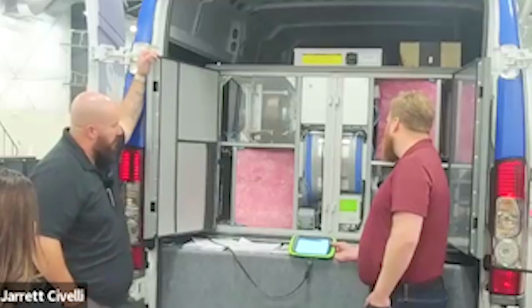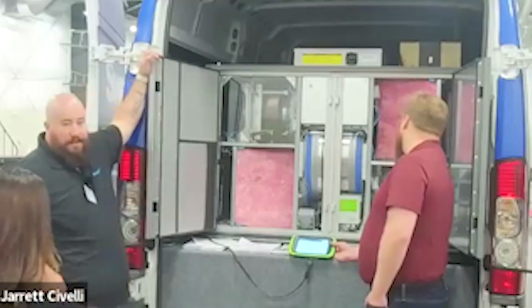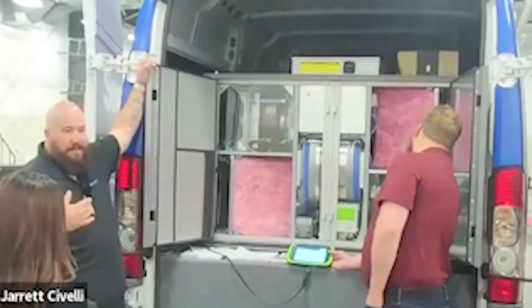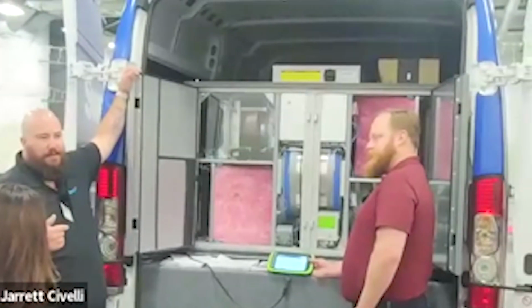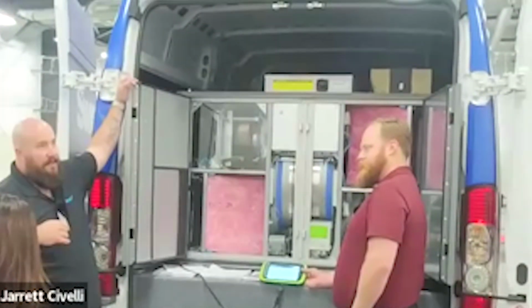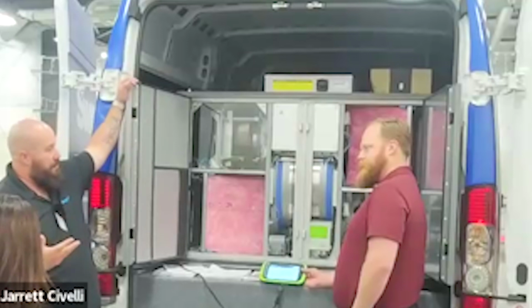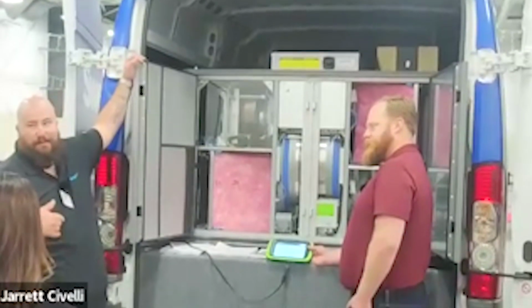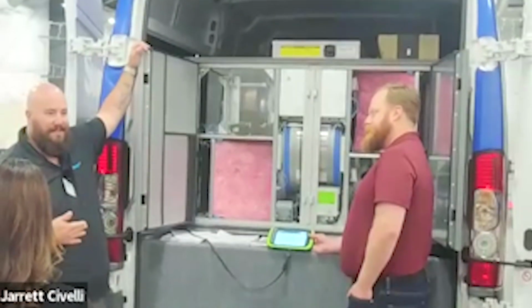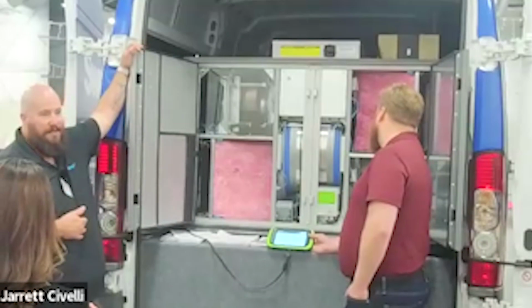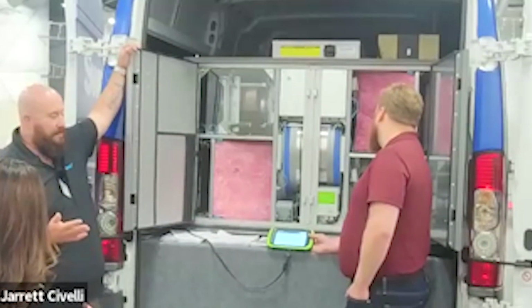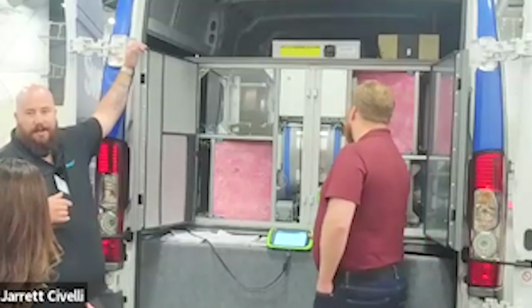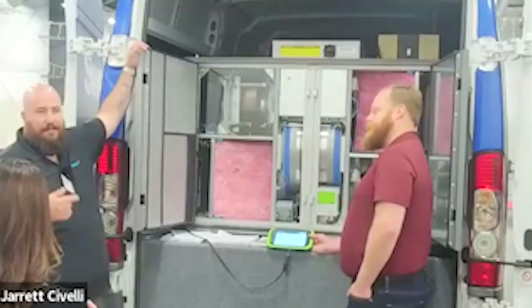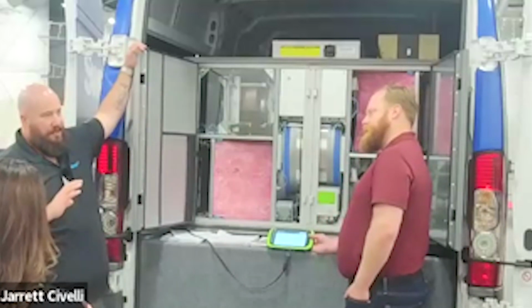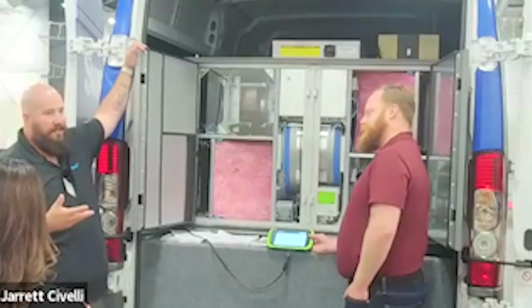Another thing that I didn't mention: in all of their algorithms, the fan knows how often it's spun. An issue with wheel heat exchangers is that they're self-cleaning, but only if they rotate every once in a while. If they sit stagnant for a long period of time and air is blowing across just one side, it's going to get dirty. So it tracks the amount of time that the wheel spins and occasionally rotates it just so that it cleans itself.